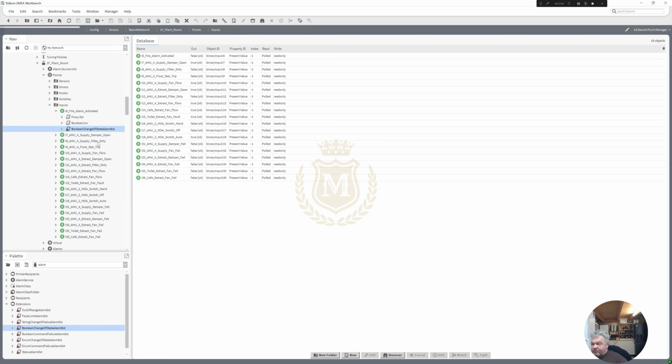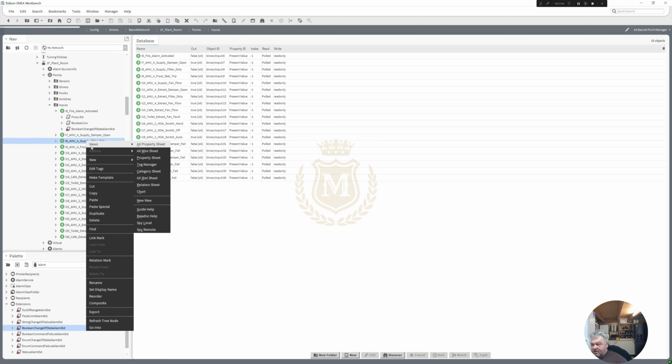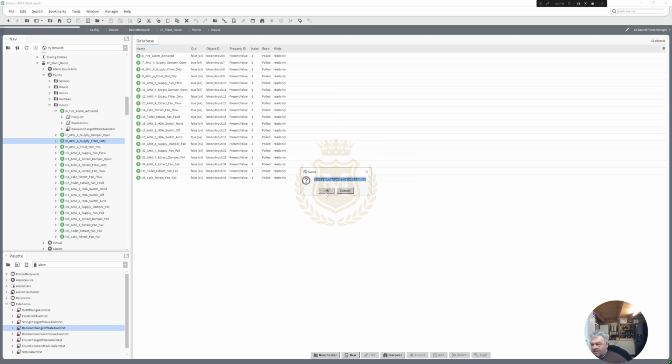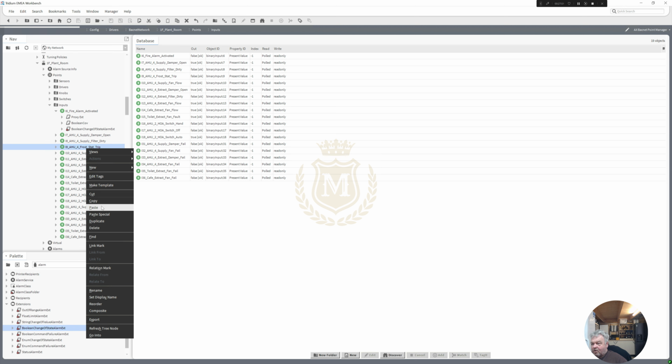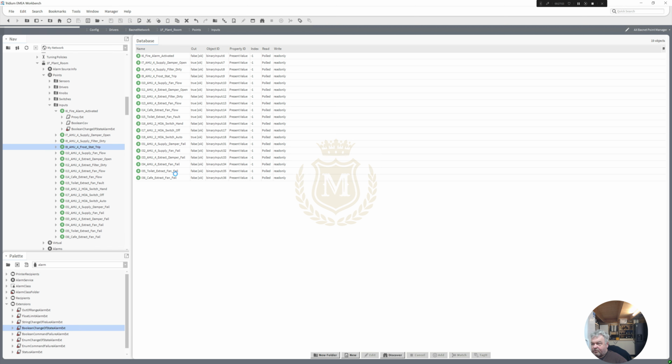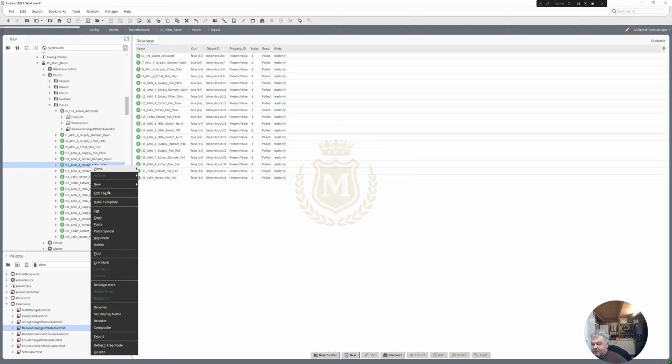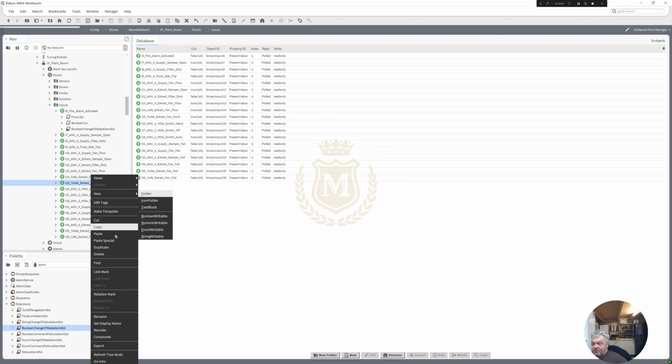Damper open, not interested in that. Filter dirty, yes. Frost stat trip, I do want to know. I want an alarm when the frost stat is tripped. Don't need that. Damper open, filter dirty, yes. We need an alarm when filter is dirty. Flow fail, fault, yes we do.